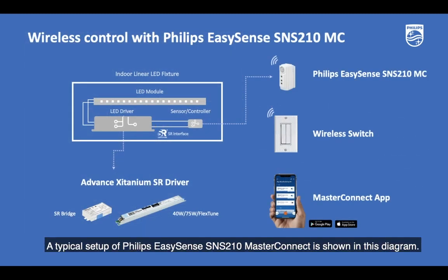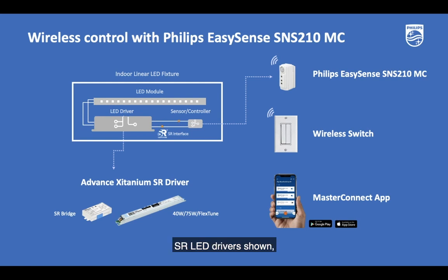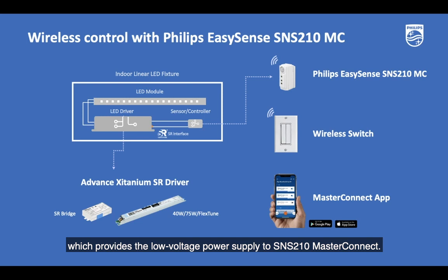A typical setup of Philips EasySense SNS210 MasterConnect is shown in this diagram. The indoor linear LED fixture needs to have one of the Advance Xitanium SR LED drivers, which provides the low voltage power supply to the SNS210 MasterConnect. The available LED driver options are Advance Xitanium SR bridge 40-watt, 75-watt, and flex-tune SR for human-centric lighting.